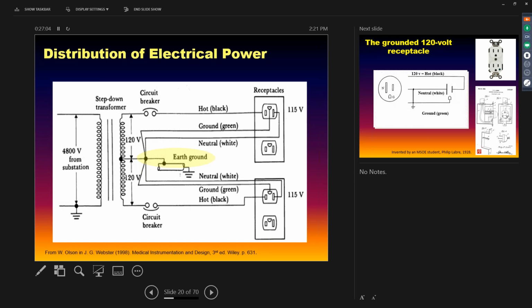Have you ever had intermittent problems troubleshooting systems where you get flaky behavior? A long time ago when I was in the hospital, I heard about measuring the ground-neutral voltage, the potential between neutral and ground. Theoretically that should be zero. If ground and neutral are bonded at one point, the voltage across those two wires should be zero or very close to it. If you start measuring 2, 3, 4 volts or so, that suggests potential issues with the earth-ground connection, which can cause flaky behavior in systems. I had a little pigtail made up with two banana plugs off the ground and neutral that I plugged into a multimeter, just something I'd routinely check. Because after multiple renovations in a space, you think things have been done properly, but sometimes you can get whacked.